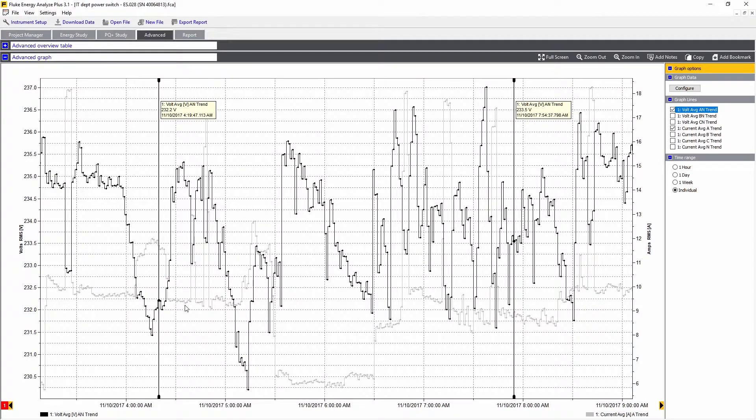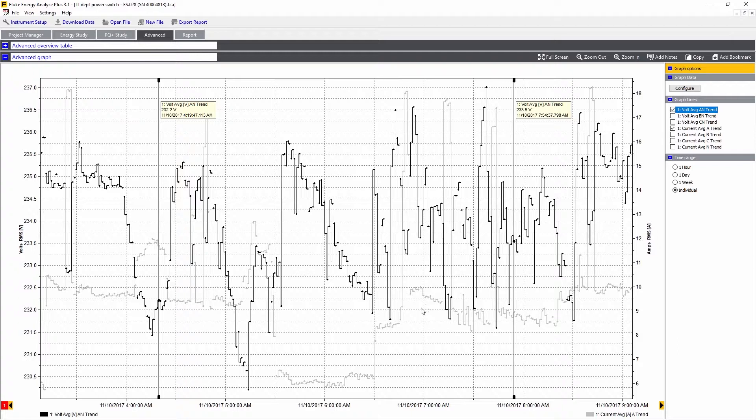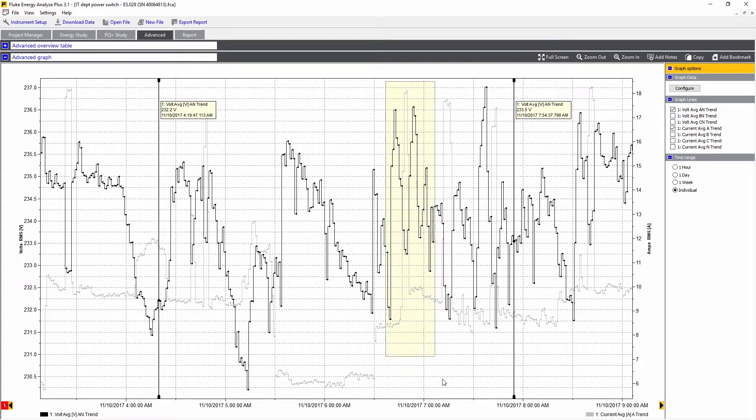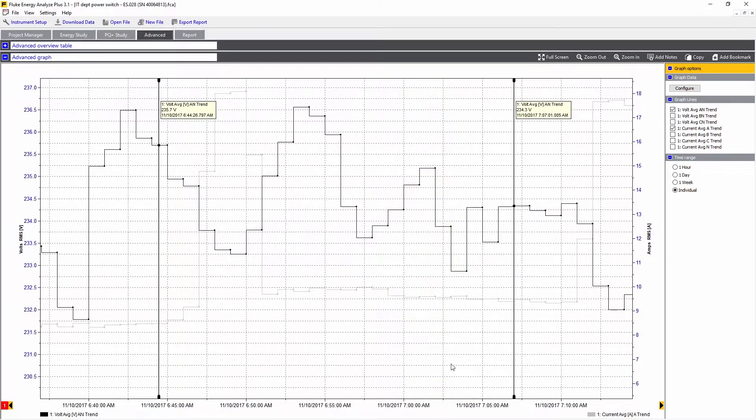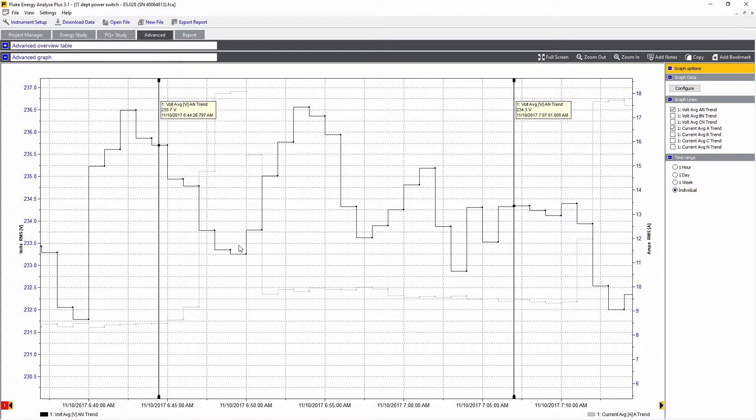Here we can see the trend of the voltage, which is the black line, and the current is the grey line. Here we see some correlation. In this case, the voltage drops based upon the current rise, so some load must have switched in to see that happen.